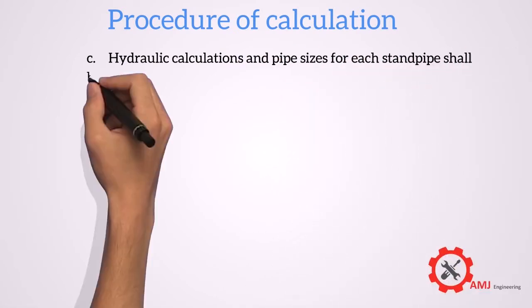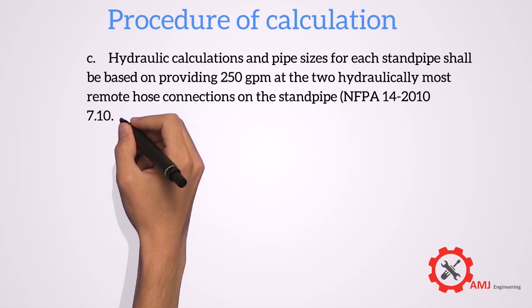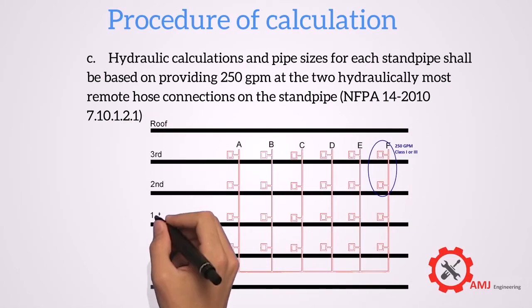Hydraulic calculations and pipe sizes for each standpipe shall be based on providing 250 GPM at the two hydraulically most remote hose connections on the standpipe, as per NFPA recommendation.